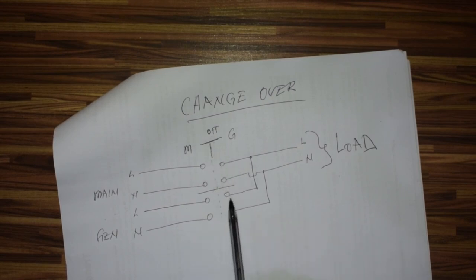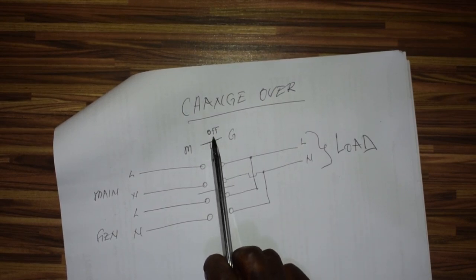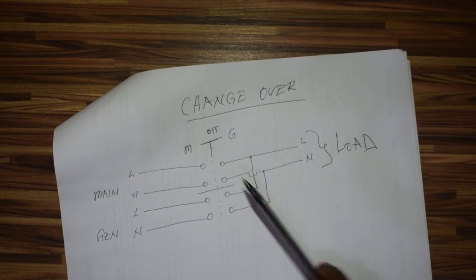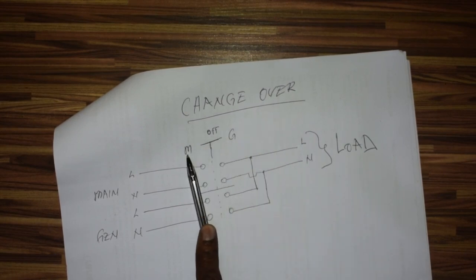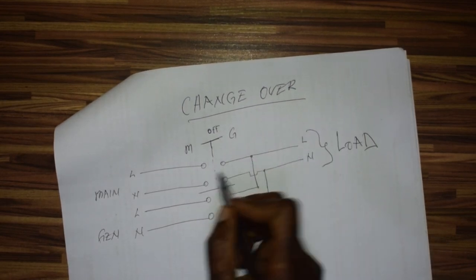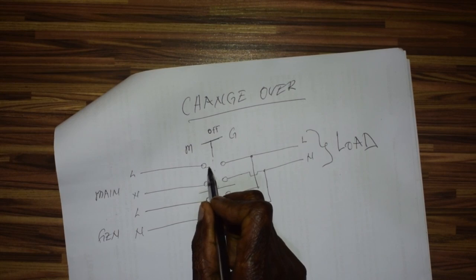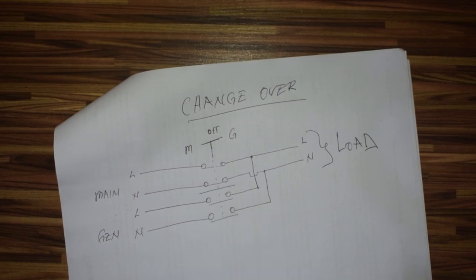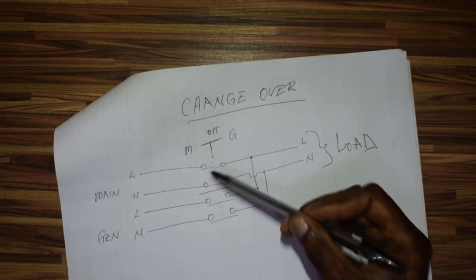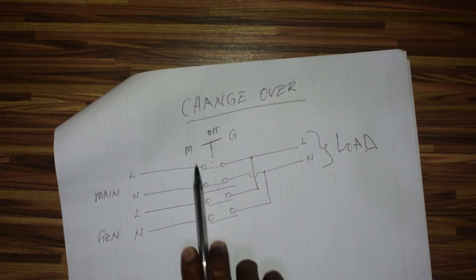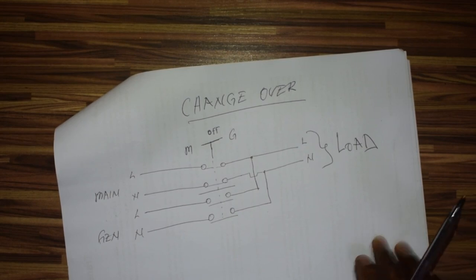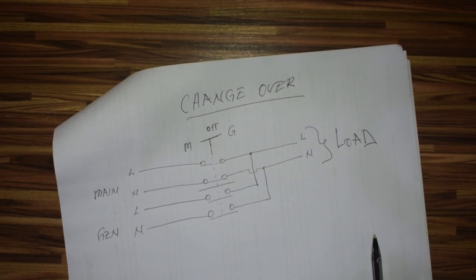If the knob is in the off position, that simply means all these contacts are open - neither gen nor main, no power. You turn the dial to M and this will close. This means these contacts are closed and these are open. If power goes, you just go and turn the dial, like the one I showed you earlier. Here it is in zero now, so this is open.